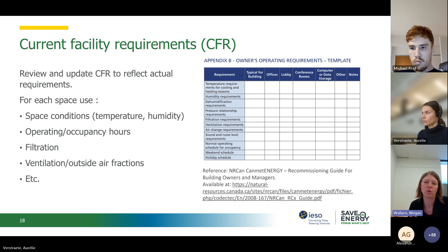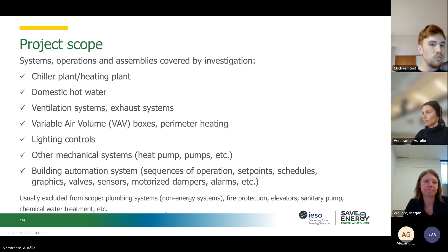So the project scope for the EBCx - you'll want to look at your chiller plant and heating plant, the domestic water systems, ventilation and exhaust systems, variable air volume or VAV boxes, your perimeter heating systems, lighting controls, other mechanical systems such as heat pumps or circulating pumps, and the BAS systems, including things like sequence of operations, set points, schedules, etc. We don't usually look at non-energy plumbing systems, fire protection, elevators, sanitary pumps, chemical treatment, or water treatment systems.